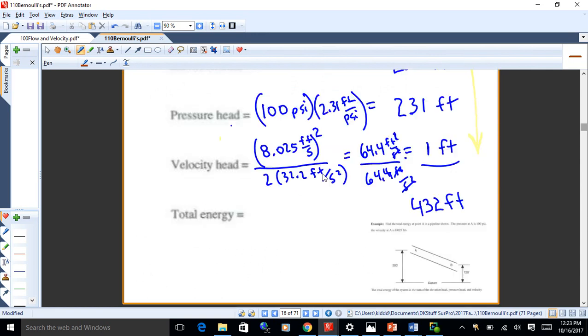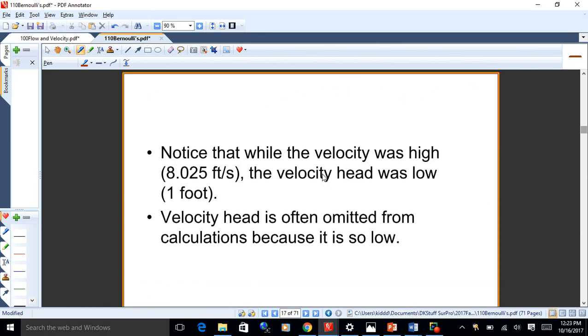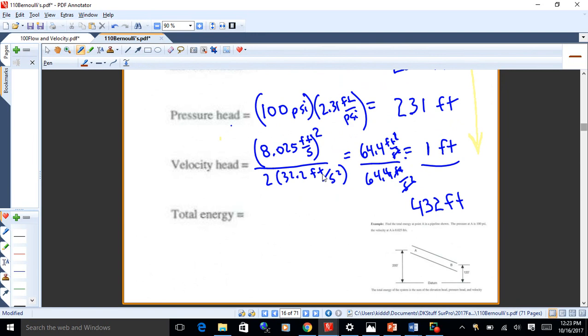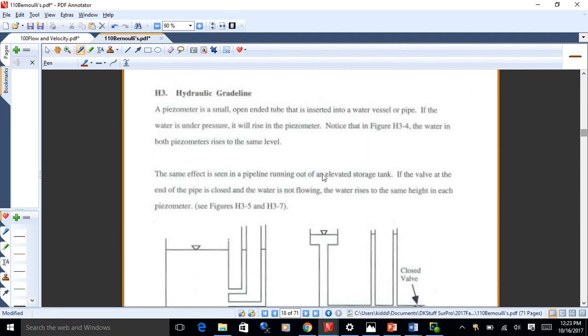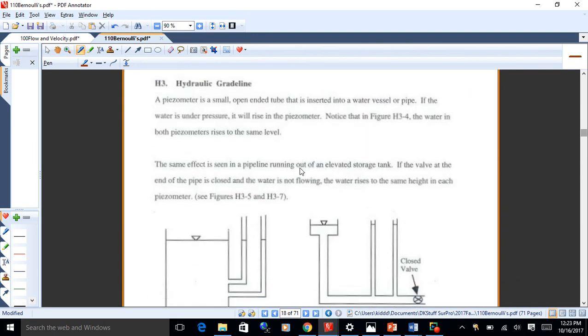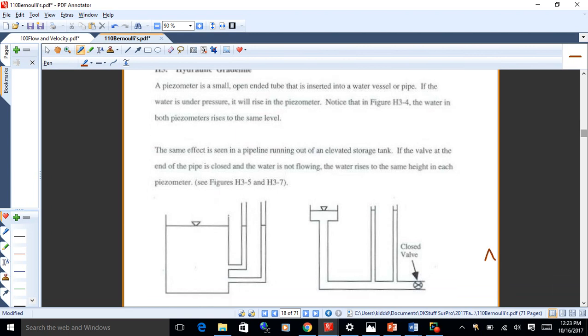All right, so this idea of energy and water is used to analyze things, and it's just kind of an important thing to understand. One thing we use it for is hydraulic grade line. A hydraulic grade line is a line that joins the points together of the elevations that the water would rise to if it were allowed to rise as high as it wanted to.